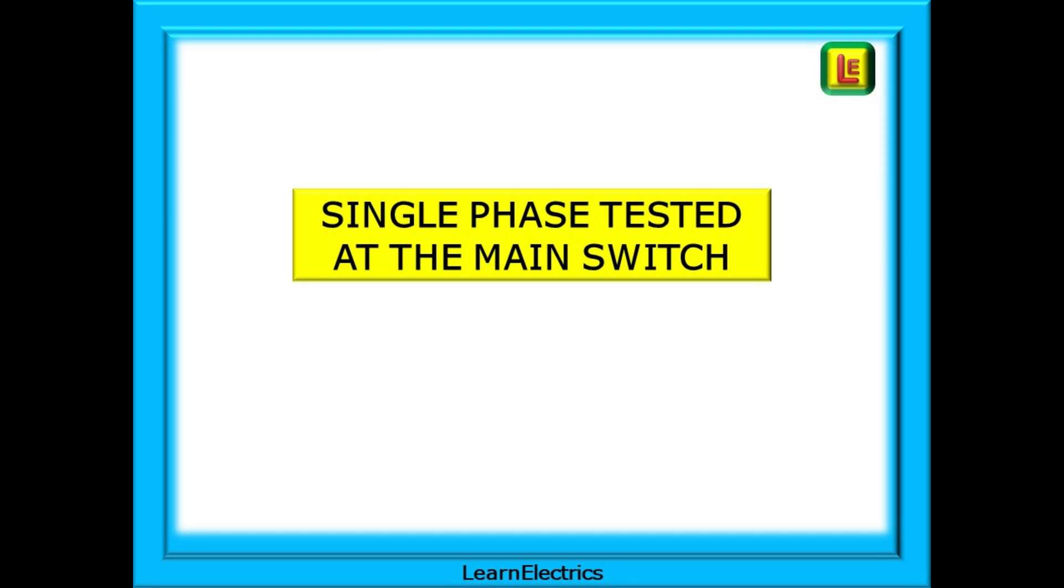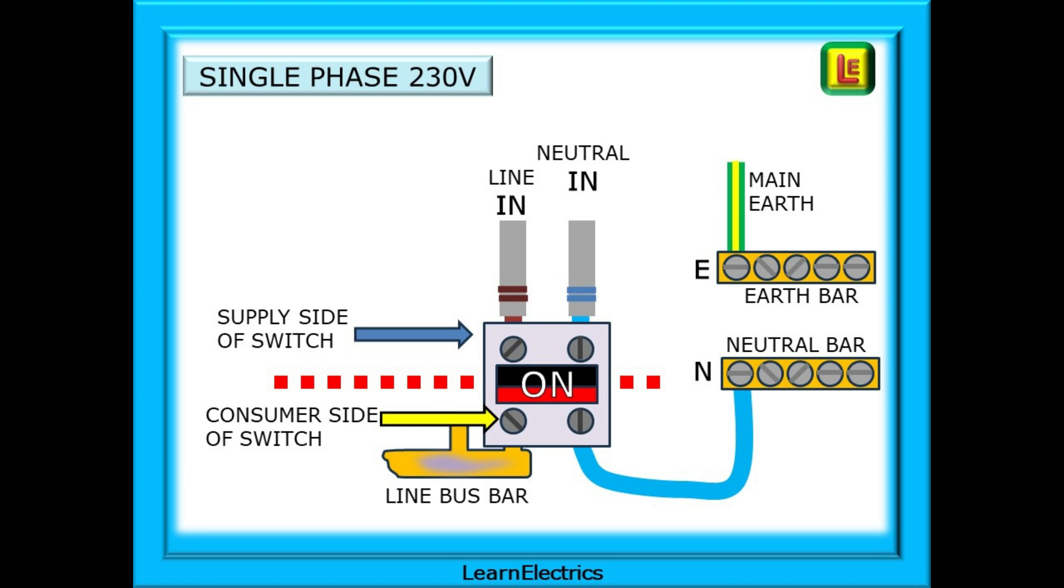Let's look at these, and we can begin with a single-phase consumer unit that is to be voltage tested at the main switch. This is the main switch, and in most domestic consumer units, the live feed, the incoming feed or supply, will enter the top of the switch. This part of the switch, the top two terminals, will always be live. The bottom two terminals are on the consumer side of the switch and these are switched on or off by the switch. One terminal is connected to the bus bar for the circuit breakers, and the other terminal is connected to the neutral bar. The main earth would go directly to the earth bar without being switched.